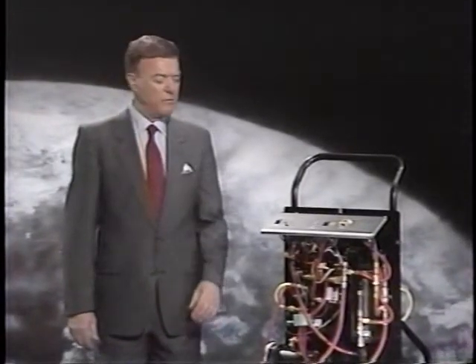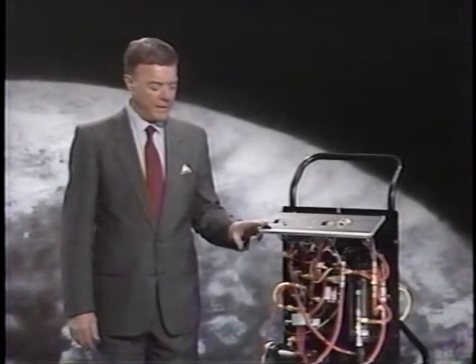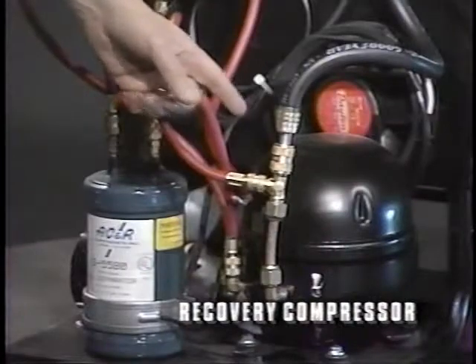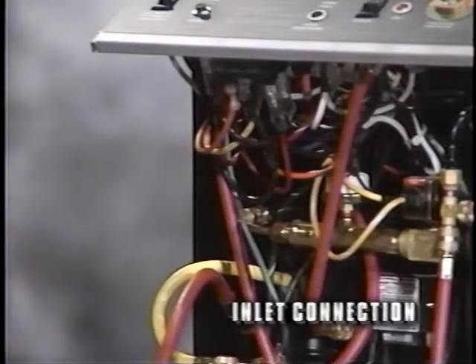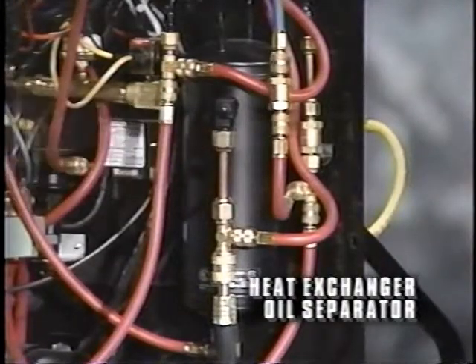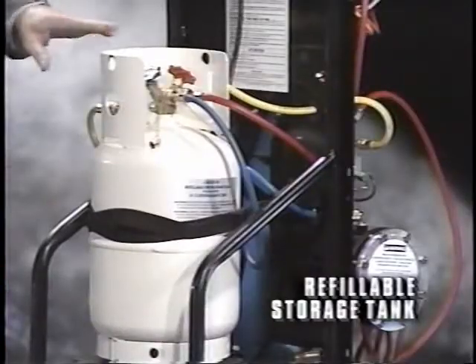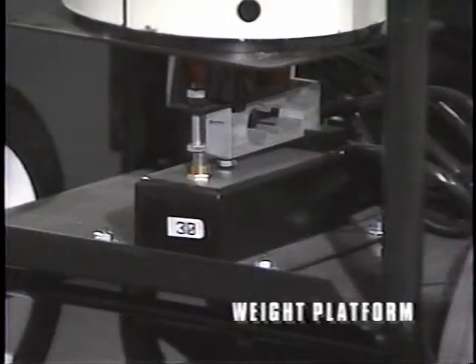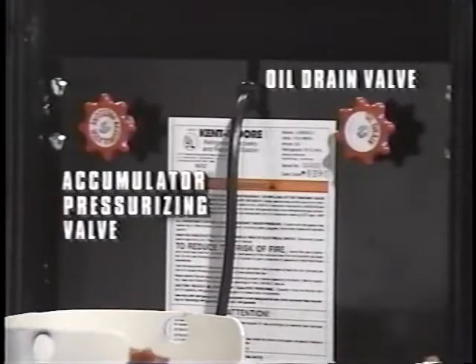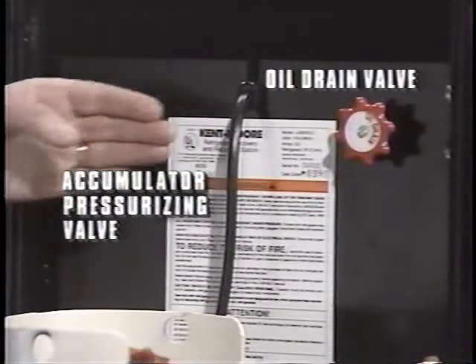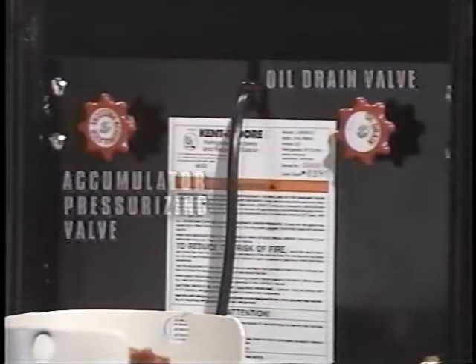Let's look at the recovery components first. The recovery phase utilizes the control panel, a recovery compressor, an inlet connection, a heat exchanger and oil separator, a refillable storage tank, a weight platform, an accumulator pressurizing valve, and an oil drain valve.